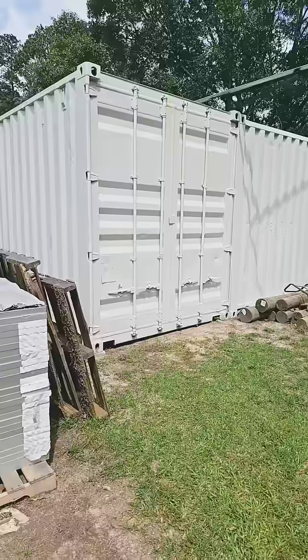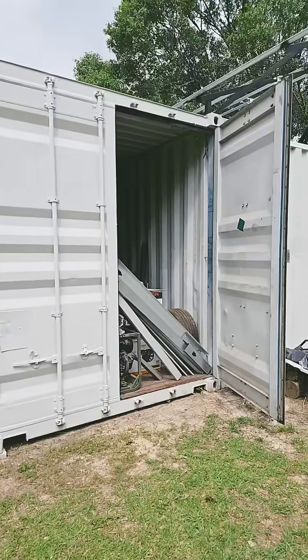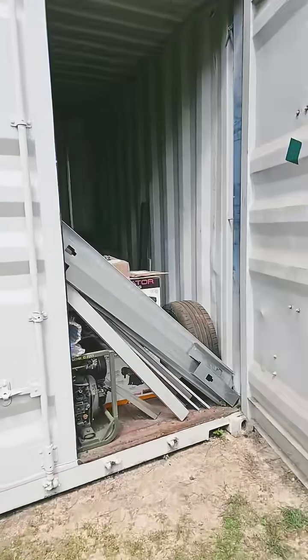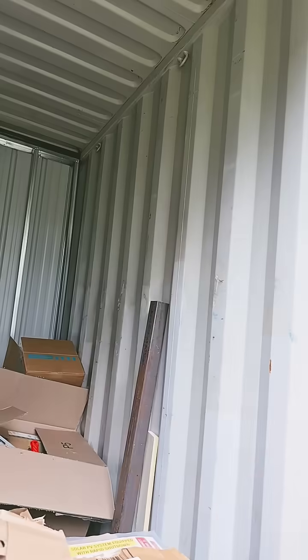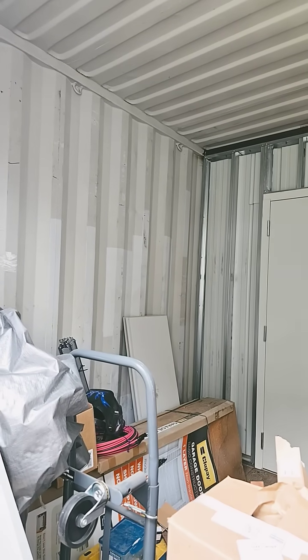There it is from down here, and from back here we got to put those three pieces on. This is going to be the solar shed running to my electrical service. Inside this shipping container — once I move all my junk out of the way — I'll be mounting a Tesla Model 3 LFP pack on the wall, and on this side I'll be installing two Solis 11.4 kilowatt inverters.